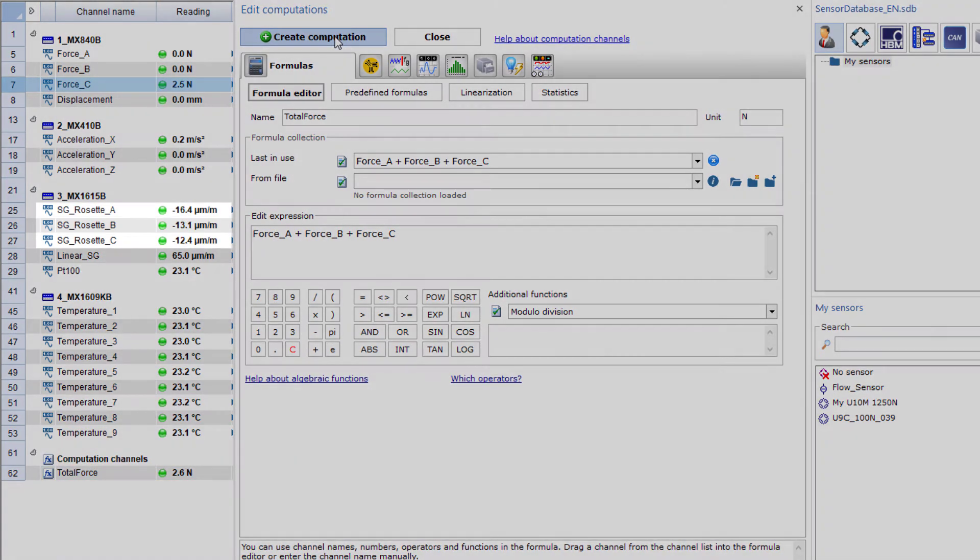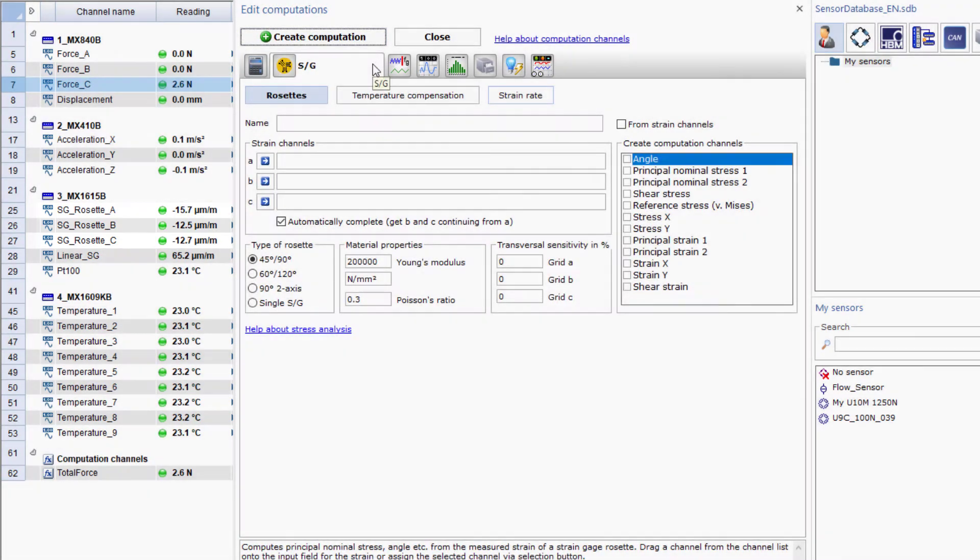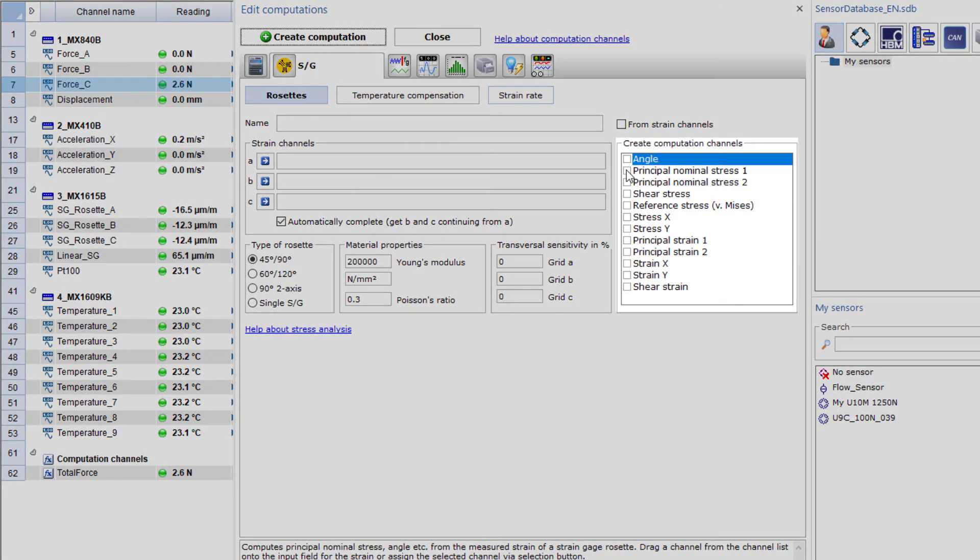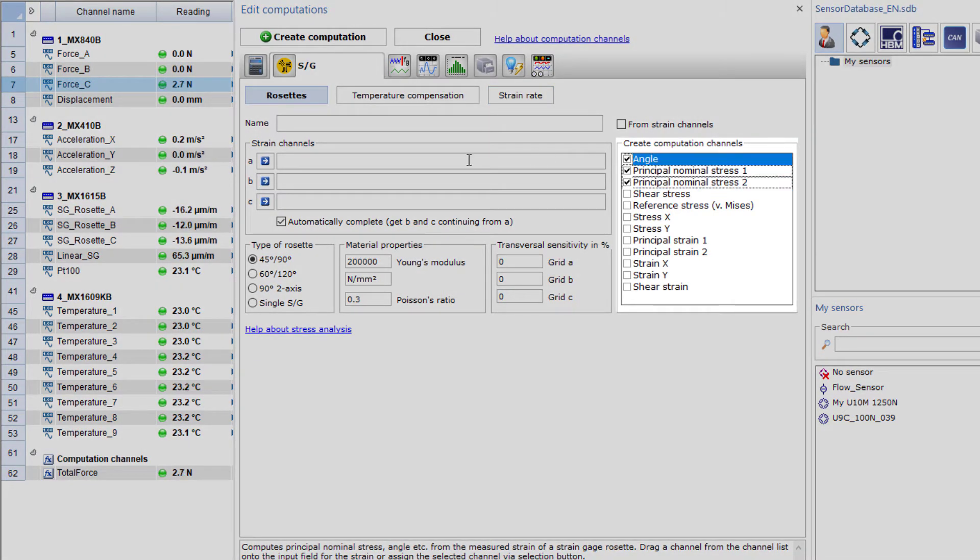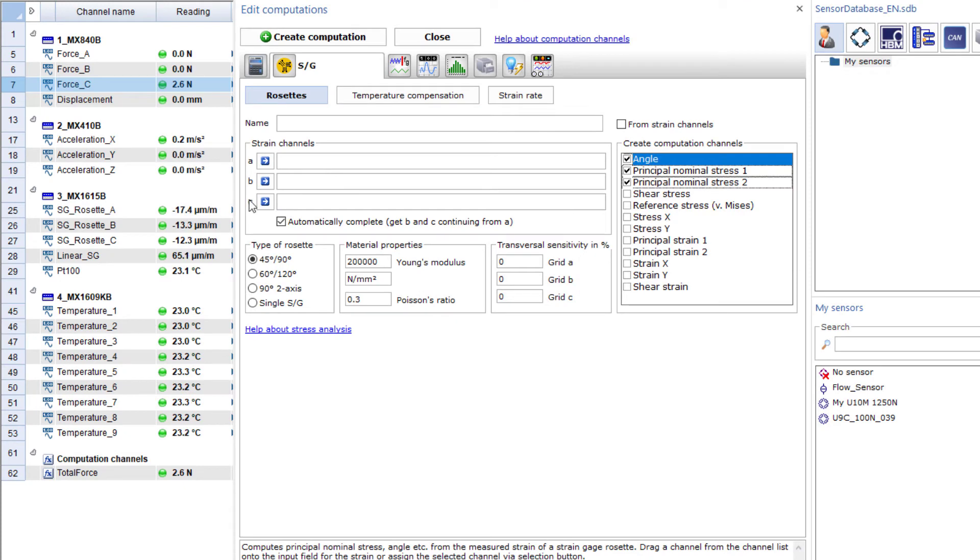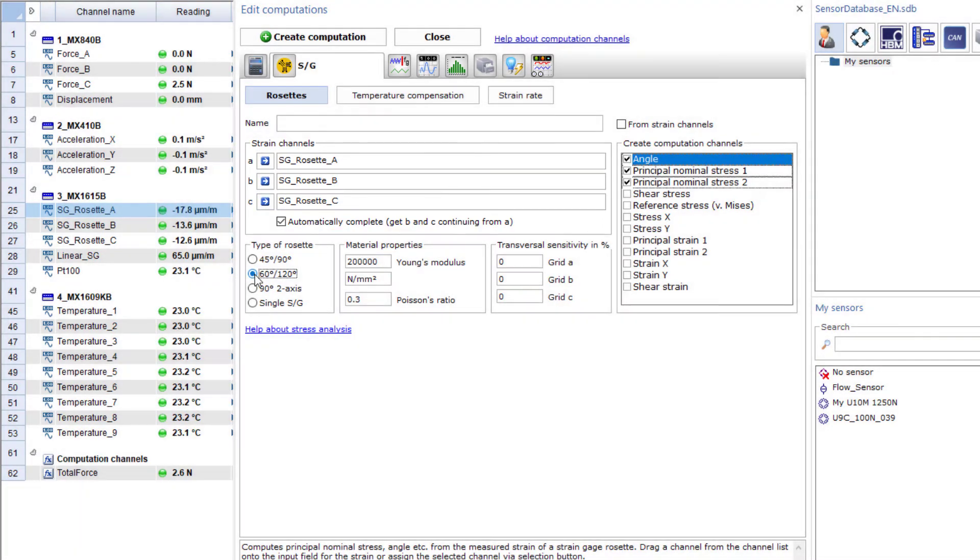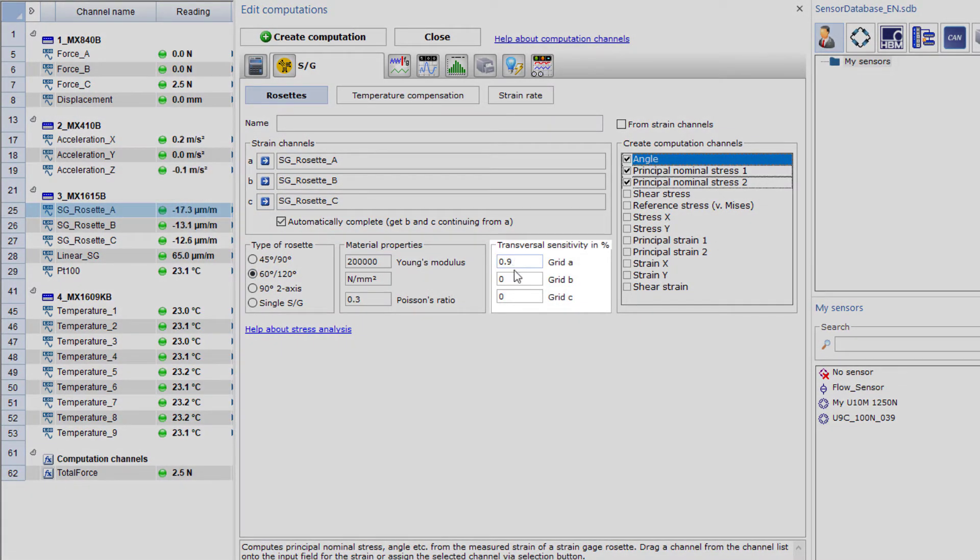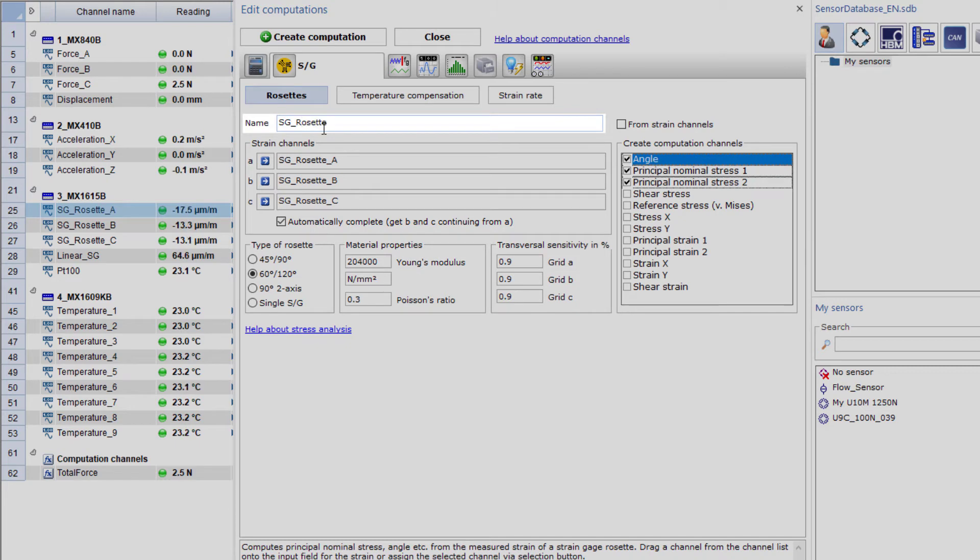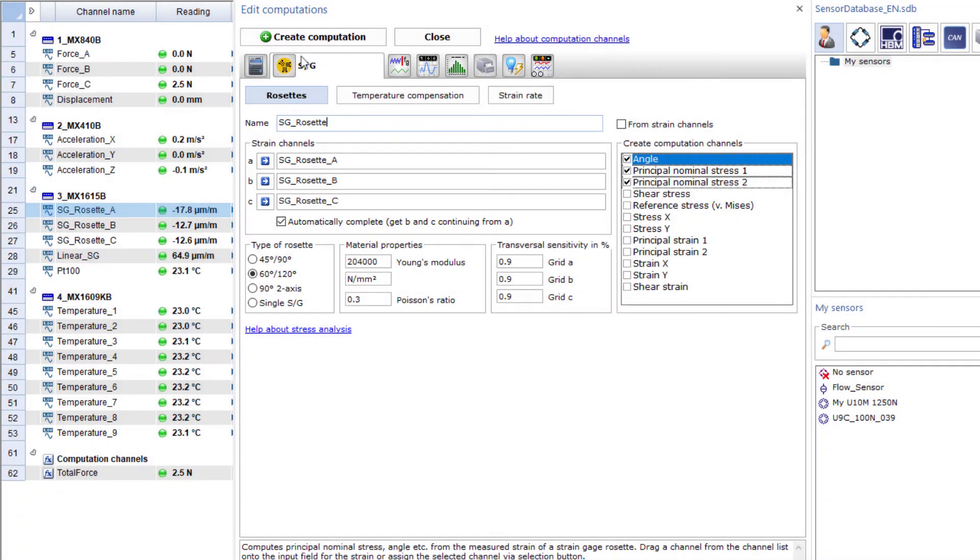The strain gauge rosette is measured in these three strain channels. Here, I would like to calculate the principal stresses 1 and 2 as well as the angle. For this purpose, I'll use drag and drop to add the first channel to this calculation. The following channels are then automatically added by Catman. I can find the necessary parameters for the calculation on my strain gauge package and enter them here. I'll also add the material properties and assign a name so that three more calculations are created with one click.